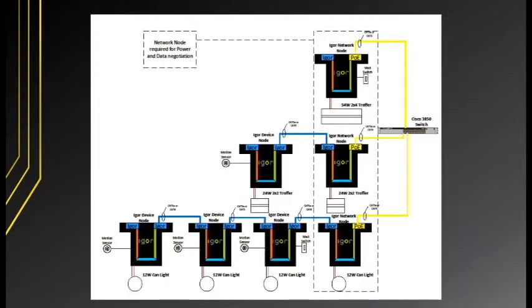All right, so a few more details about the Igor daisy chain capabilities. As we mentioned before, the node types on this slide are 60 watt Rev 5 nodes. And so those are designed for up to 60 watts per total daisy chain, including power for nodes, fixtures, sensors, et cetera. That 60 watts also has to take into account any line loss on that home run from the data closet out to the first network node, which usually is pretty minimal.